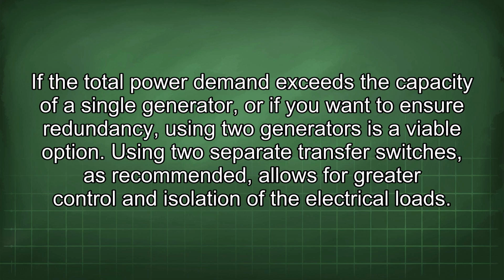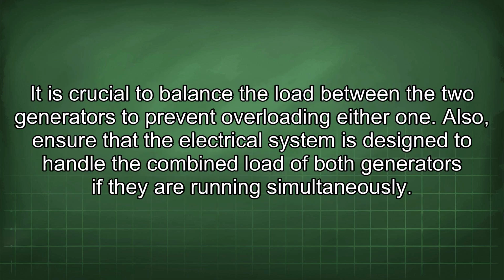Using two separate transfer switches, as recommended, allows for greater control and isolation of the electrical loads. It is crucial to balance the load between the two generators to prevent overloading either one. Also, ensure that the electrical system is designed to handle the combined load of both generators if they are running simultaneously.